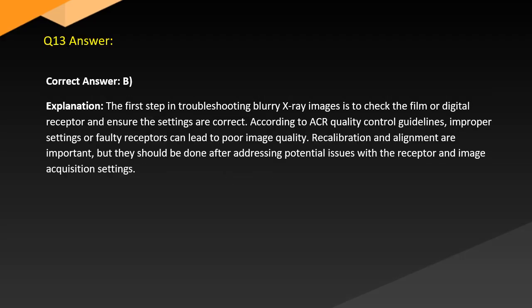Answer. Correct answer: B. Explanation. The first step in troubleshooting blurry X-ray images is to check the film or digital receptor and ensure the settings are correct. According to ACR quality control guidelines, improper settings or faulty receptors can lead to poor image quality. Recalibration and alignment are important, but they should be done after addressing potential issues with the receptor and image acquisition settings.